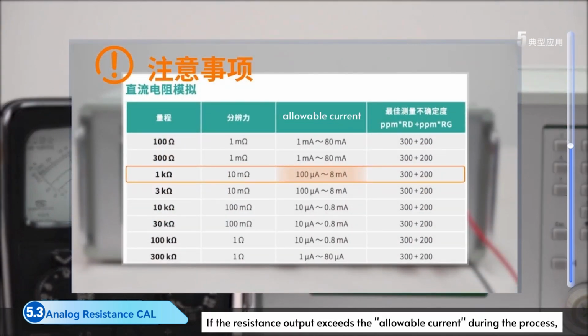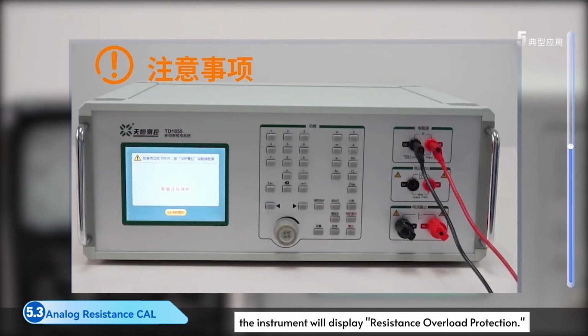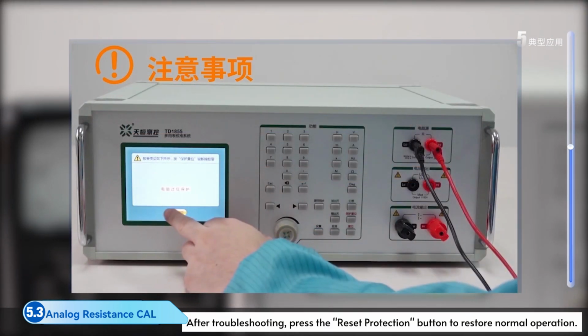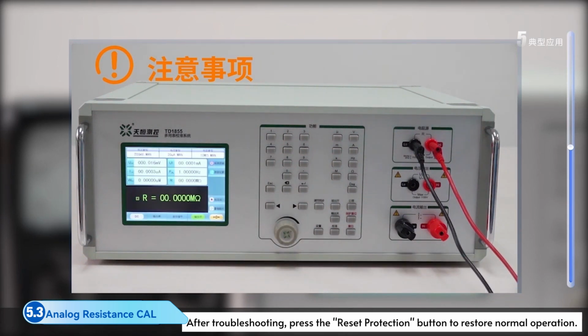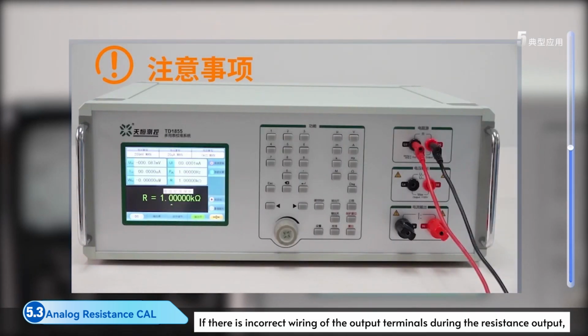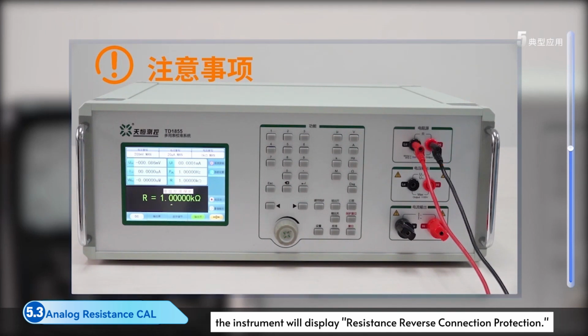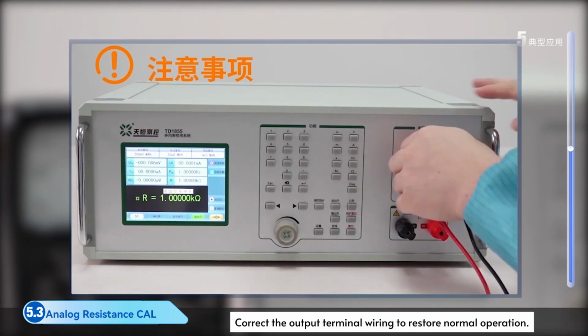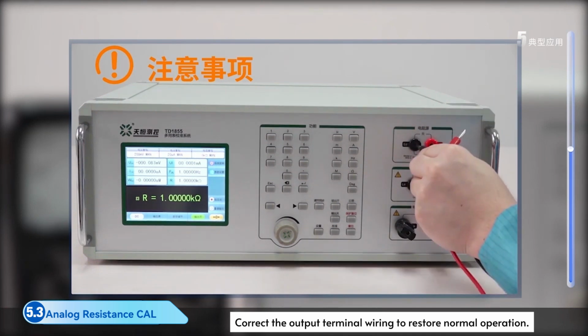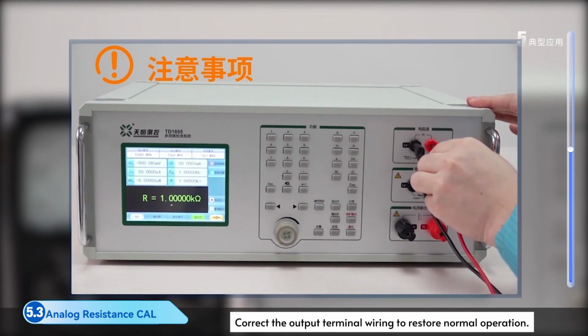If the resistance output exceeds the allowable current during the process, the instrument will display resistance overload protection. After troubleshooting, press to restore normal operation. If there is incorrect wiring during the output, the instrument will display resistance reverse connection protection. Correct the output terminal wiring to restore normal operation.